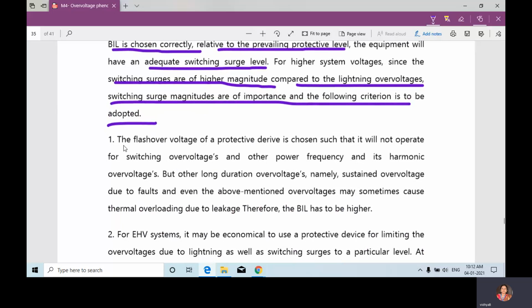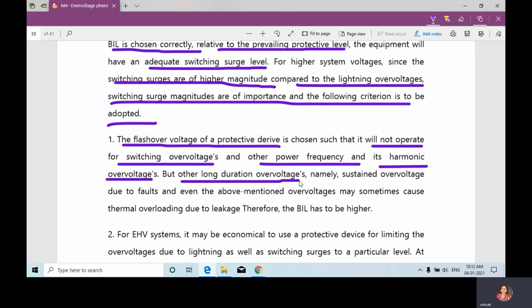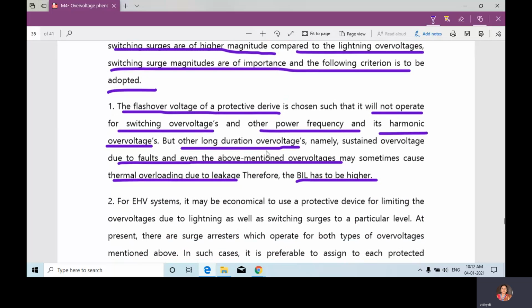That is, the first criterion is the flashover voltage of a protective device is chosen such that it will not operate for switching over voltage and other power frequency and its harmonic over voltages. But other long duration over voltages, namely sustained voltages due to faults and even the above mentioned over voltages, may sometimes cause thermal overloading due to the leakage. So BIL has to be higher. Okay, they are saying that BIL has to be higher. Why? Because the flashover voltage of the protective device is chosen so that it will not operate for switching over voltage and also for power frequency and harmonic over voltages.